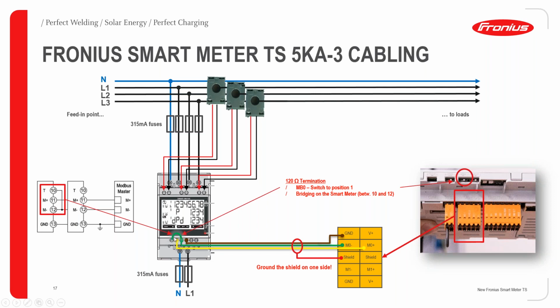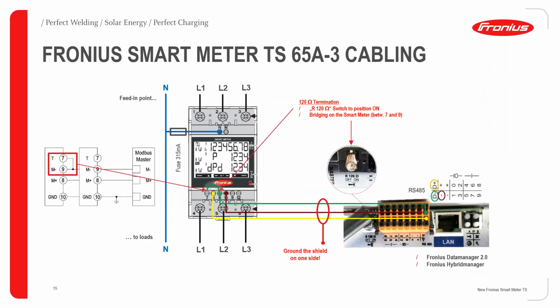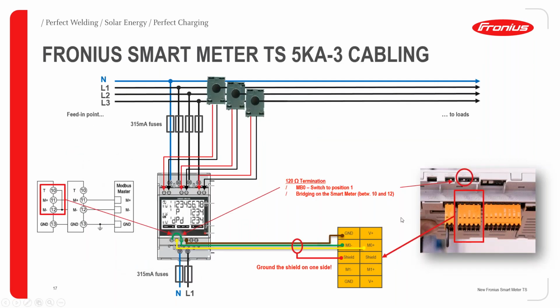And then the smart meter 5KA3 also has the same terminal resistance. You have to bridge this connection point 10 and 12. If you see it in the previous smart meter, the numbers are 7 and 9. Here it's 10 and 12. So just pay close attention to the quick guide or the manual whenever you're doing it. So bridge a cable between 10 and 12, then you are turning on the terminal resistor.